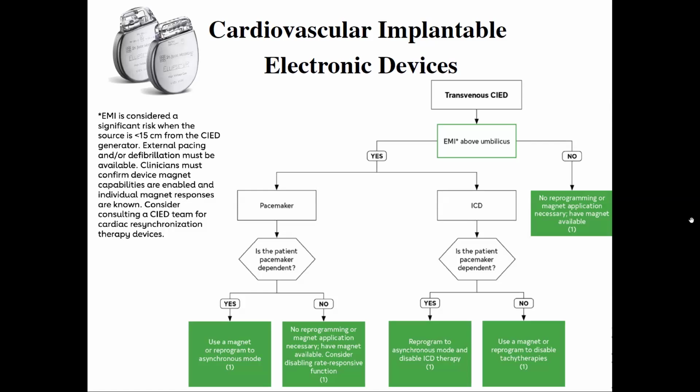But if there's going to be continuous cautery of a tumor bed above the umbilicus and they're dependent and it's a defibrillator, they should be reprogrammed. So that's a unique situation.